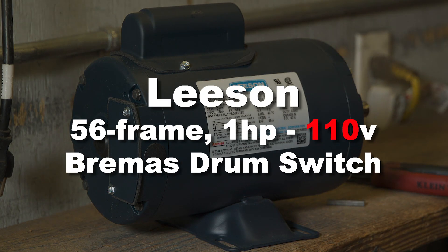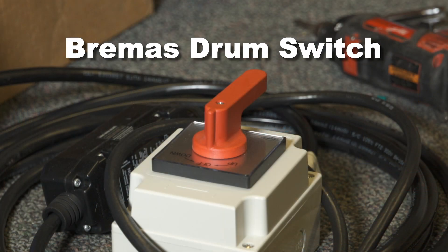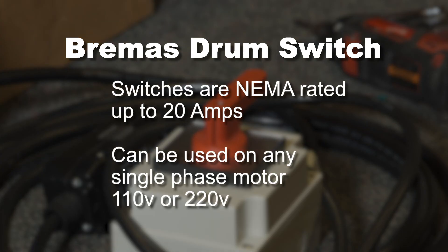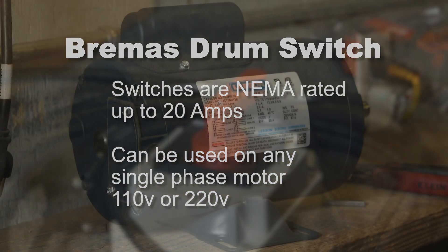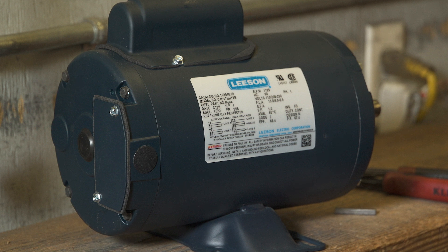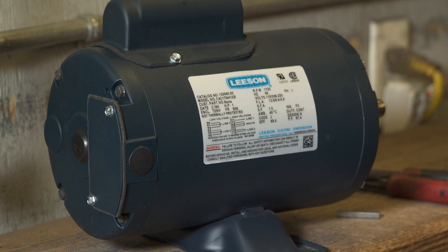In this video we're going to show you how to properly wire a Leeson 56 frame 1 horsepower motor to the Bremas brand drum switch for 110 volt use. Bremas brand switches with red handles are supplied by BHUSA. They are NEMA rated up to 20 amps and can be used on any BHUSA supplied single phase reversible AC boat lift motor from three-quarter horsepower through one and a half horsepower, both 110 volt and 220 volt.